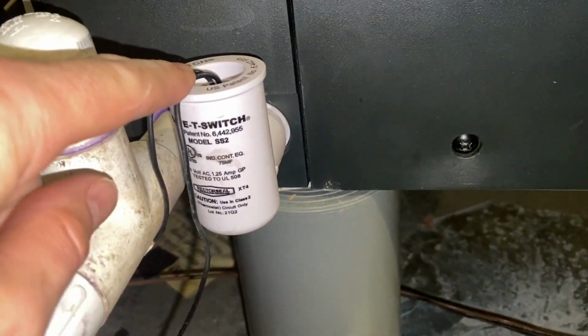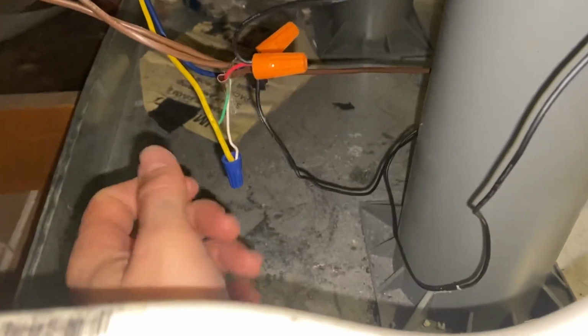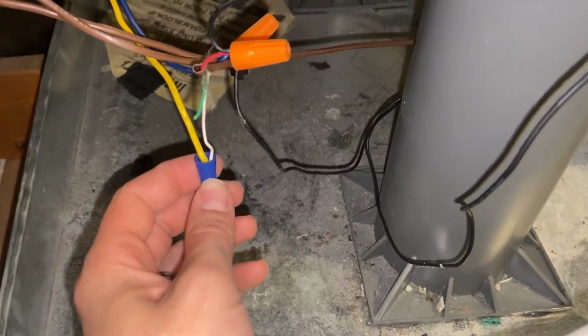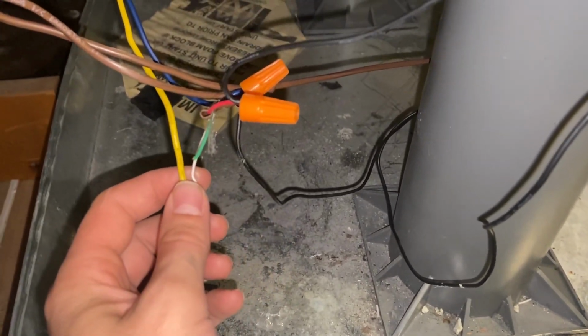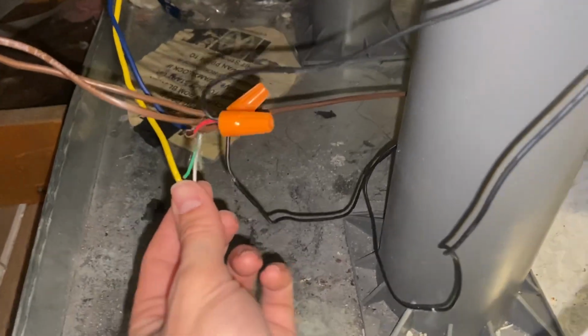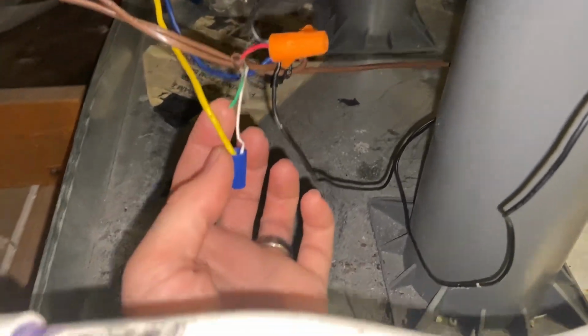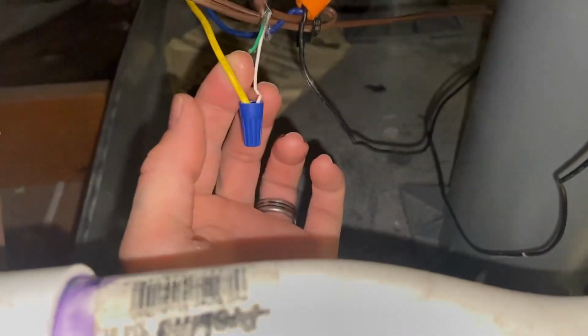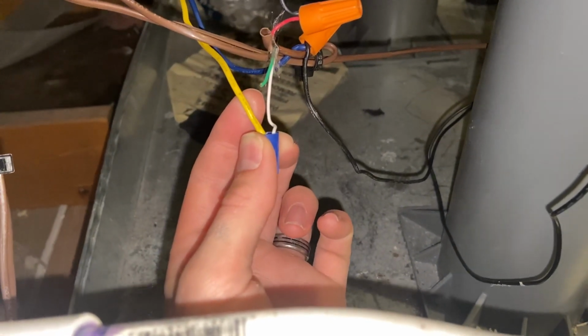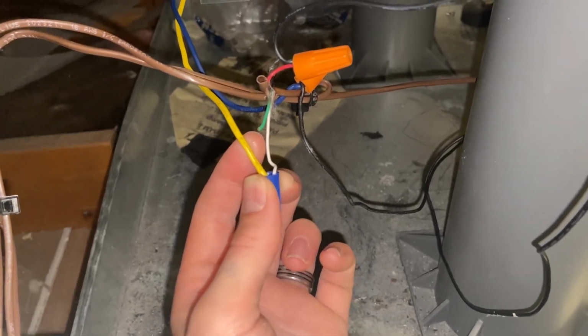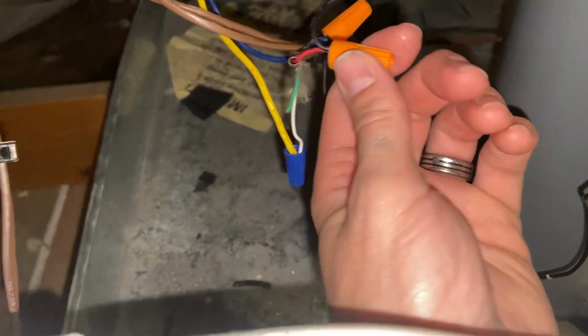And the other switch here is for the backup of the condensate drain. Basically what you can do, in my case, I just got my multimeter again and probed the constant hot side of the transformer. So this yellow wire connects directly to the zoning panel, that white wire up there is this wire right here. So that's a direct connect, and then all the switching is done on the other leg.